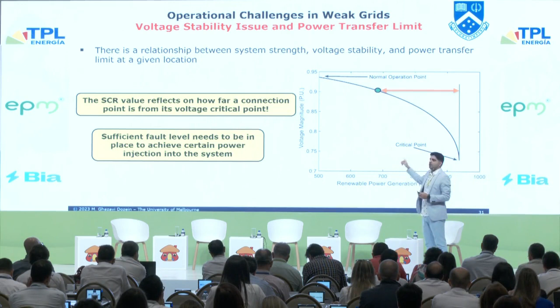Now we are adding renewables, adding inverters, and taking out synchronous machines. Maybe you can add synchronous condensers, and this is what is happening in the South Australian network. The system operator invested in synchronous condensers, adding 3 to 4, each 600 megavolt-amp, to ensure we have sufficient fault level to integrate more renewables.